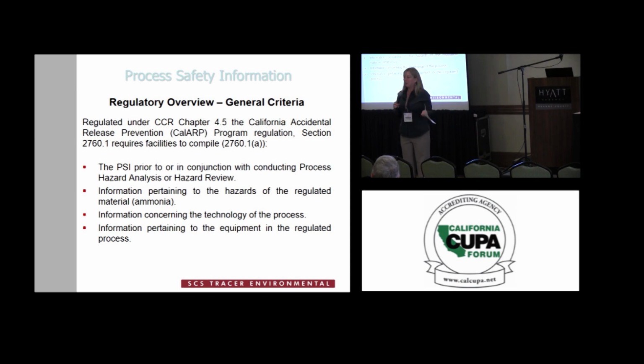Because in ammonia world, sometimes they call things a suction trap or an accumulator or a pump package or a recirculator, and there's different lingo. So there could be discrepancies between what's on the PID, what's actually out in the facility labeled on the vessel, and what's in the equipment listing. In this particular facility, there's a mistake on the piping diagrams for the compressors. They list one of the relief valves at 250 when actually they're set at 100.